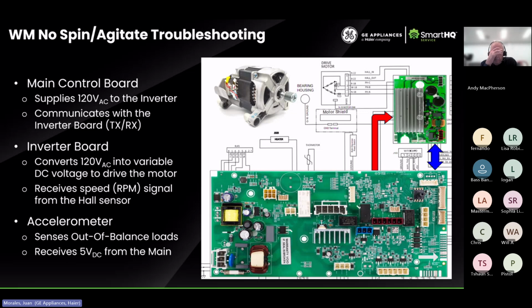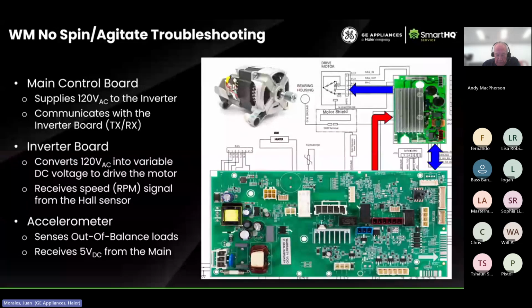Once the inverter receives the 120 AC and the signal to drive the motor, it's going to generate DC voltage to the motor. Now, this is voltage you cannot measure. The only thing you can measure, the only thing you have control of, is the 120 volts going from the main to the inverter, and the low voltage going from the main to the inverter in the DC signals. Keep those two in mind, and it'll come back to us in a second.